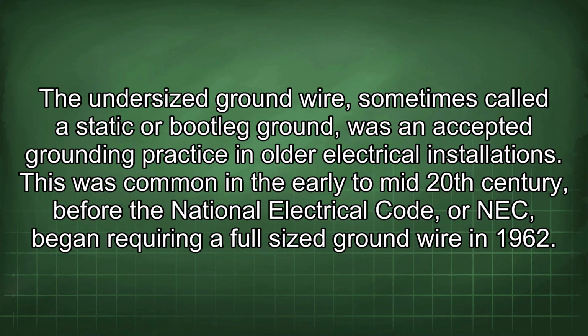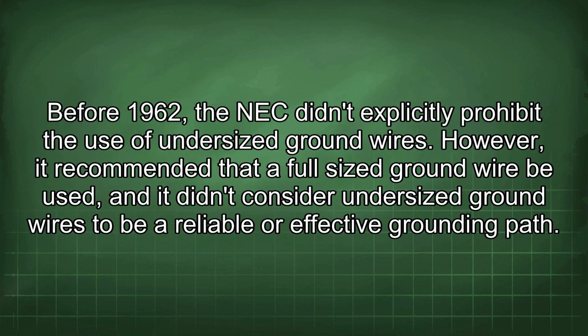The undersized ground wire, sometimes called a static or bootleg ground, was an accepted grounding practice in older electrical installations. This was common in the early to mid-20th century, before the National Electrical Code, or NEC, began requiring a full-size ground wire in 1962. Before 1962, the NEC didn't explicitly prohibit the use of undersized ground wires. However, it recommended that a full-size ground wire be used, and it didn't consider undersized ground wires to be a reliable or effective grounding path.